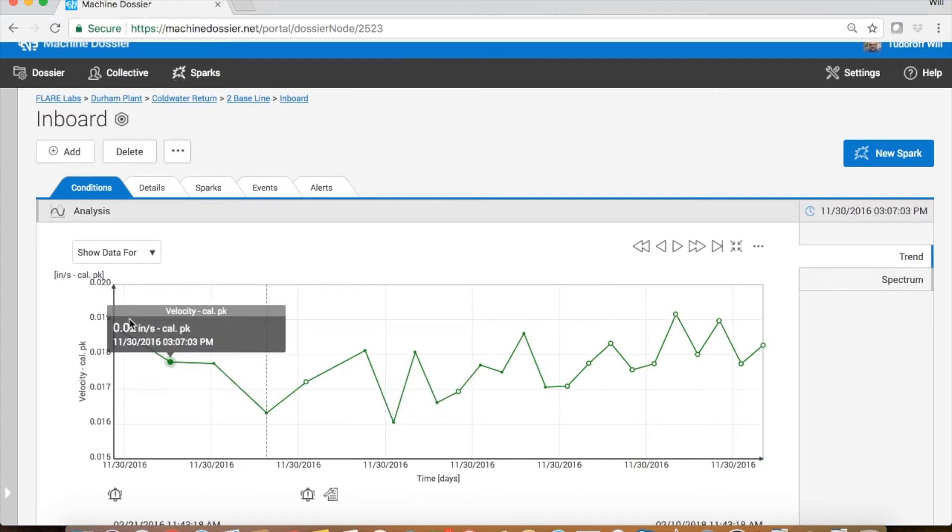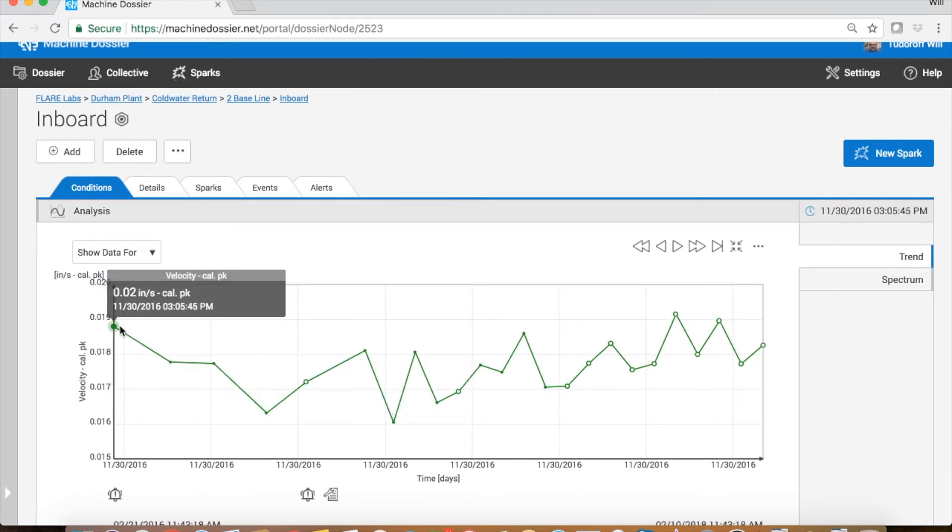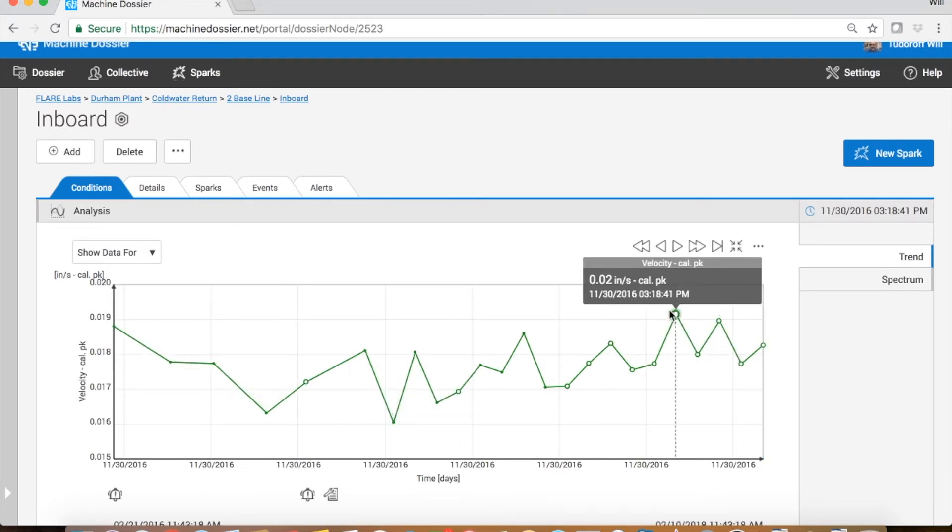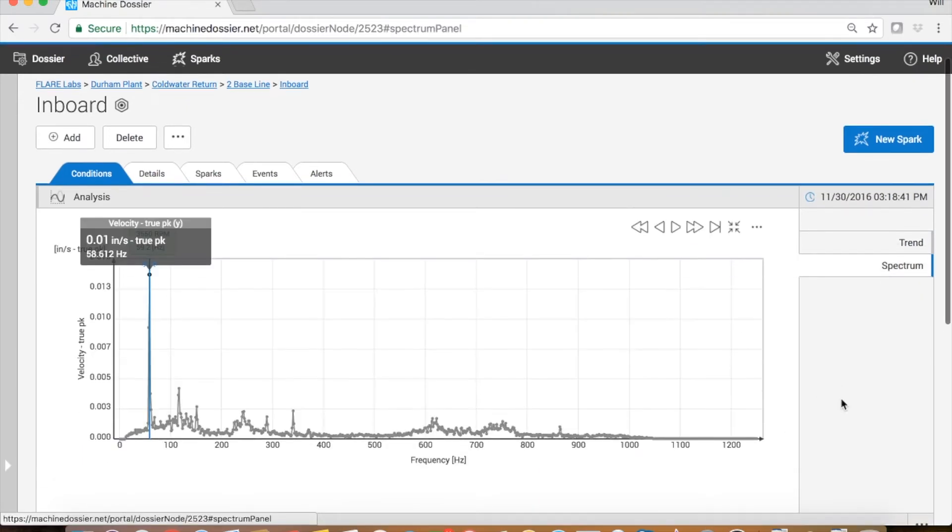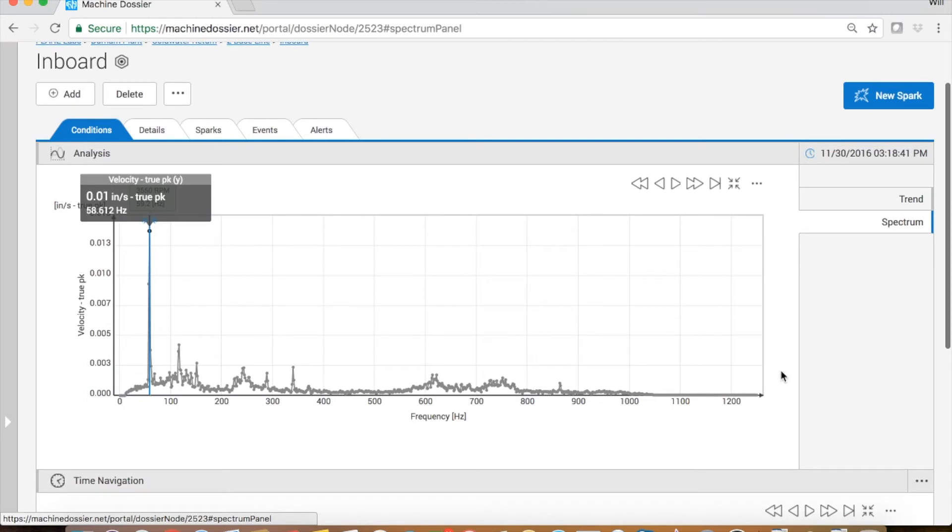And to really look at the baseline, we need to get into the spectral data, the individual frequency components that were collected and that made up that overall vibration number. So we'll click on the right hand side of the screen under spectrum and we see our baseline spectrum.